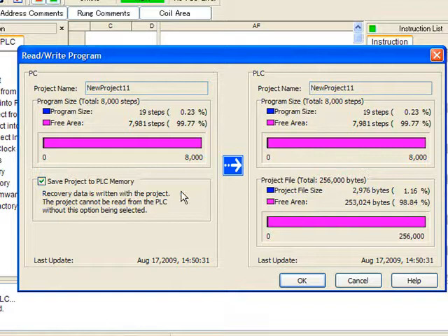Now, where you'll see this happen is with people who build equipment and may not want their documentation in the PLC for people to view. In that case, they're going to uncheck the box. But this is a very powerful feature and brings a lot of new power to the PLC world, because we can download all the documentation and we don't care anymore who's got the master disks, as we call them, who's got the project files on their laptop, because if I check that box, it downloads all the documentation into the CPU.